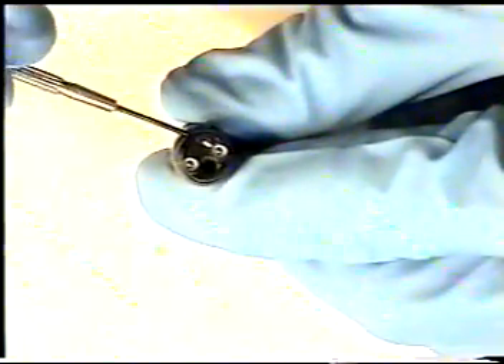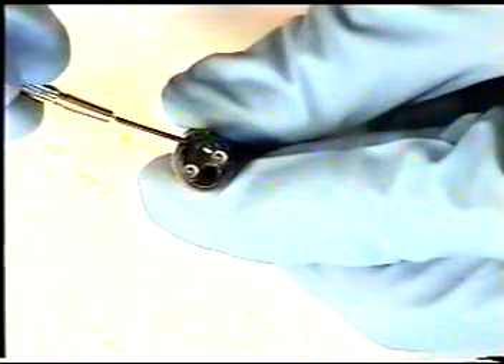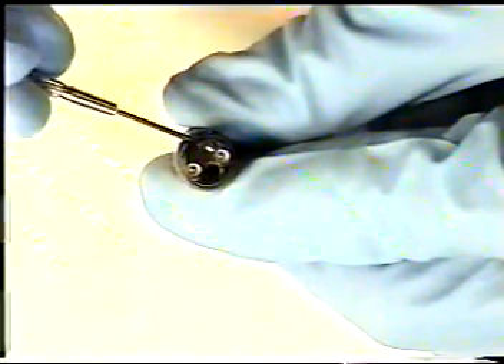Using your number 1 screwdriver, unscrew the set screw counterclockwise to release the air water nozzle from the distal end. Using your number 1 screwdriver, carefully pry out the air water nozzle from the distal end. Using your X-Acto knife, carefully clean out existing black RTV from the air water nozzle hole.